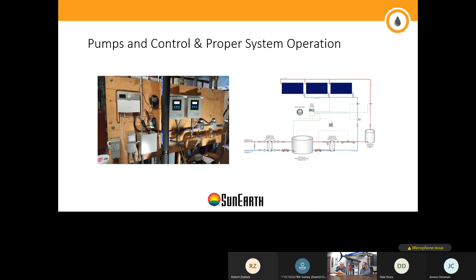So when you're running larger pumps, you usually have relays that the controller will activate, or contactors if it's large pumps. So the control is just the mechanism, like an air conditioner. You have a little thermostat and it's cooling the entire office building. So that's generally how these controls are configured. They're not configured for direct power transfer. You use relays and the appropriate UL listed electrical devices to do all that.